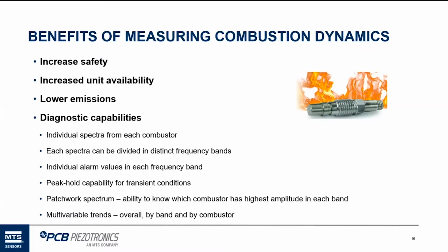Again, lowering emissions. Then you can also get a lot of diagnostic information out of a CDMS system if you have it set up that way. So you can look at different spectra on each combustor, different frequencies within the spectra. You can set alarm values on each frequency band, which a lot of plants do nowadays. You can have a peak hold when you get into a transient condition, which is convenient for long-term monitoring and trending. You can see what's been going on.